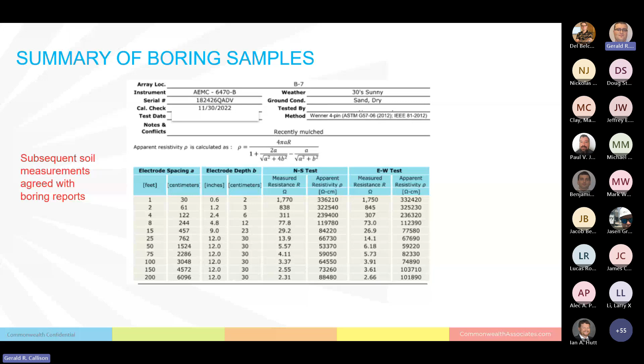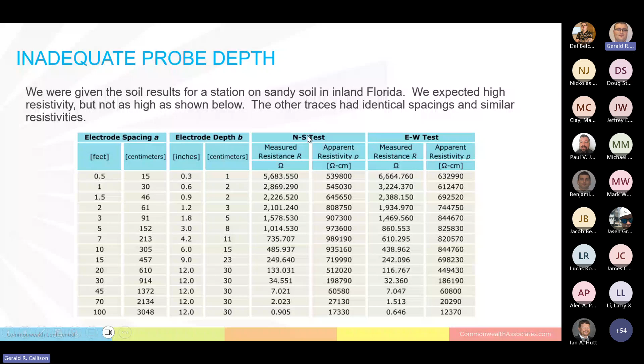Now that's really good, getting good soil contact, being careful that you're actually getting good contact with the probes. Another issue we had was inadequate probe depth. We were given soil results for a station in sandy soil in inland Florida, and we expected high resistivities because it was sand and inland, but resistivities like this, 53, 5,000, 6,000, 8,000, 9,000, it was similar throughout, above the 5 to 10,000 ohm meters range. So what jumped out at us was these shallow depths, depths of 0.3 inches. That's not very deep, and particularly in sandy soil you'll have a little bit lesser contact with the probe and the surrounding soil.